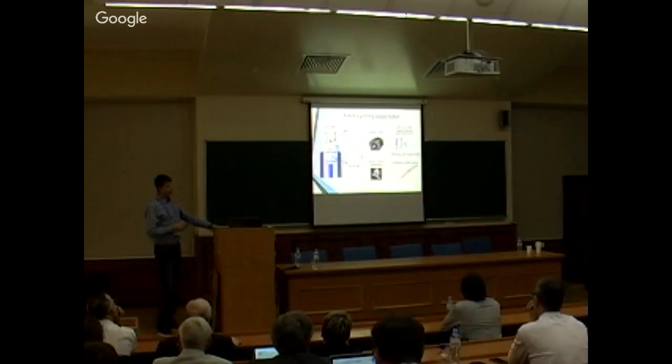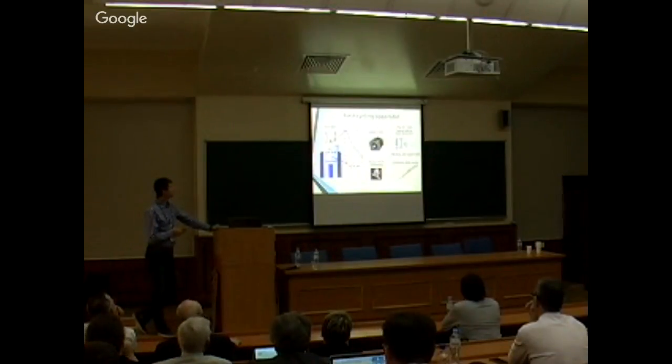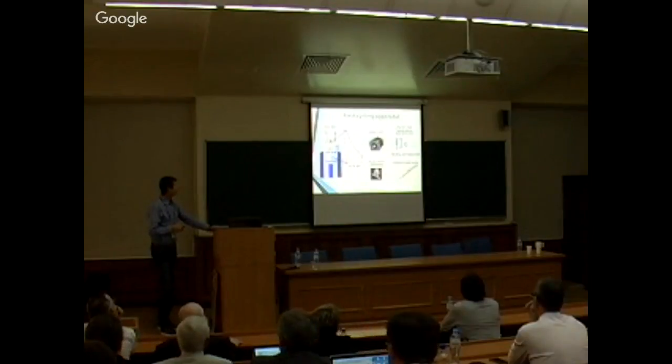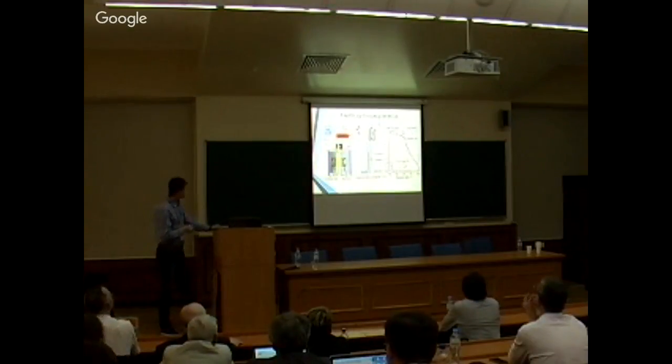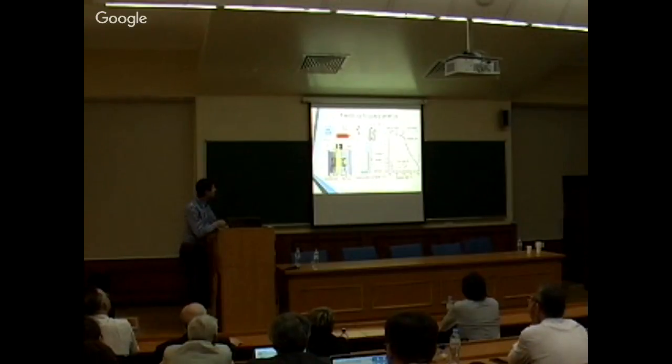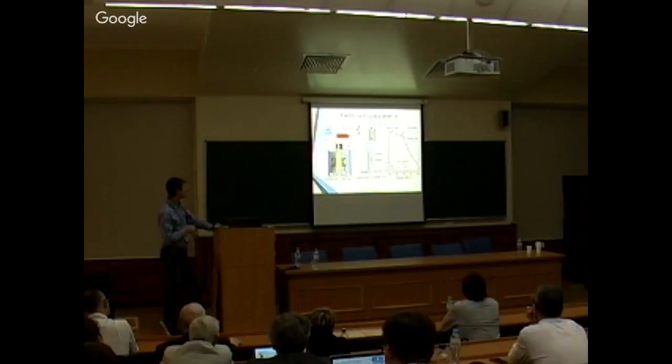On top, if we want to go lower than the Earth's magnetic field, we introduce a magnetic shield, which is made of three-layered cylinders of mu-metal. Inside we installed additional adjusting coils to change the magnetic field. Here is the scheme in detail. This is a cryomagnet. The sample is positioned on a plastic rack, which is moved up and down by the stepper motor, controlled very precisely from the NMR console. Every step is controlled by a pulse program.